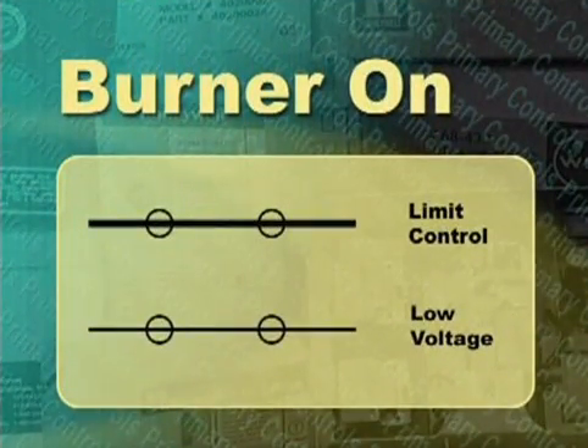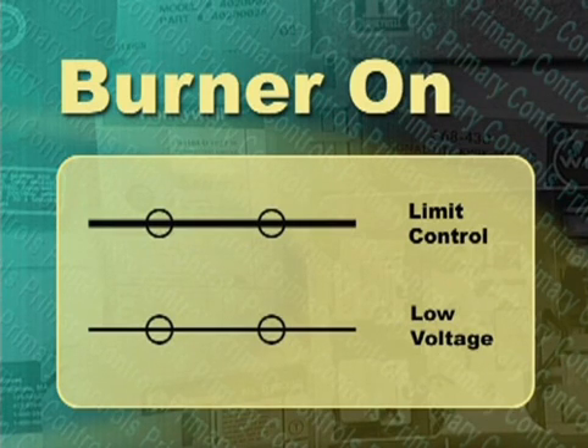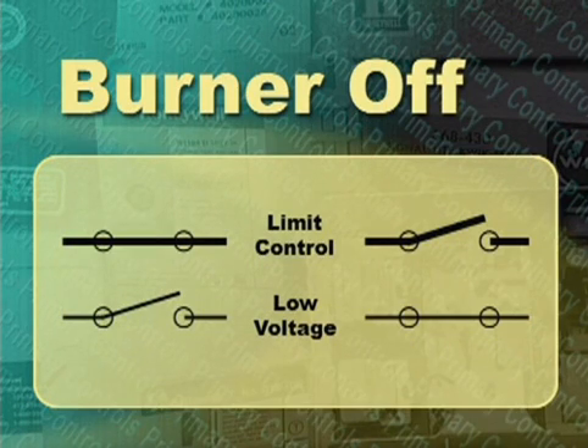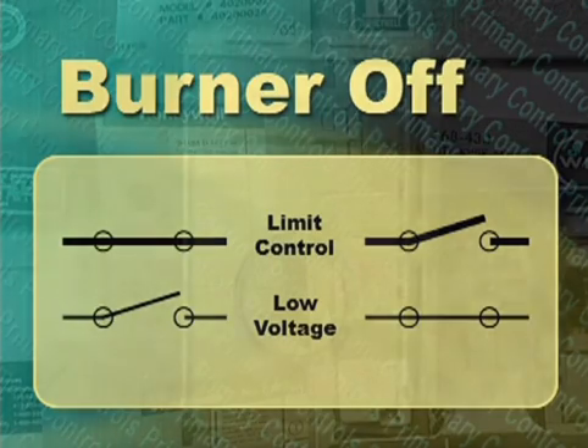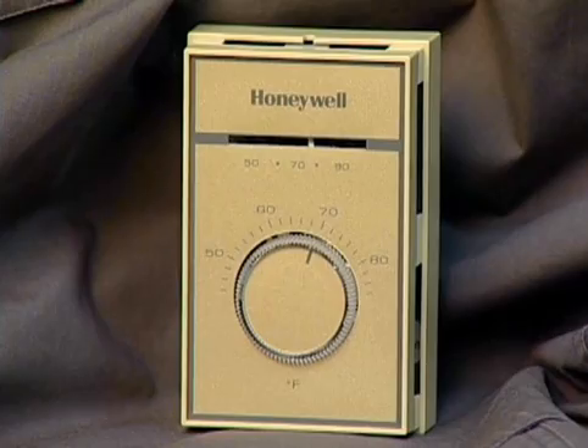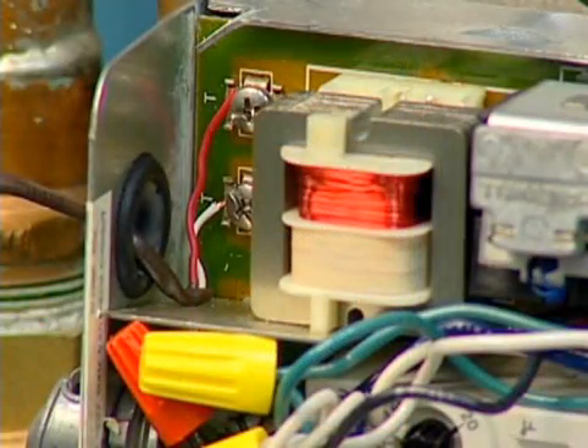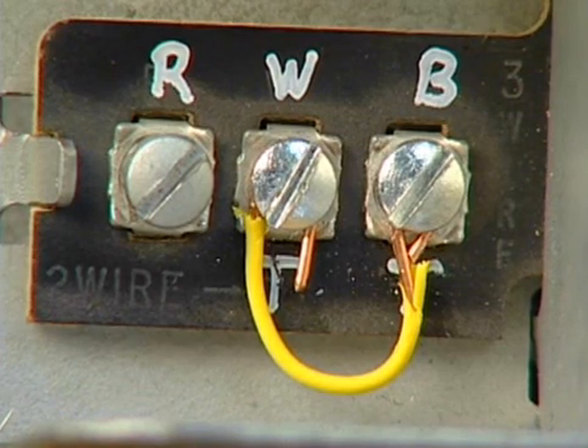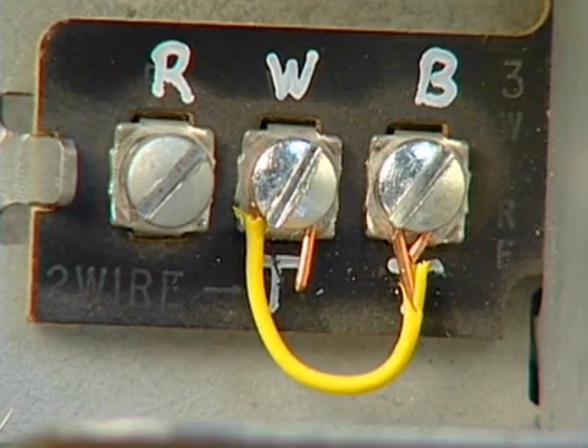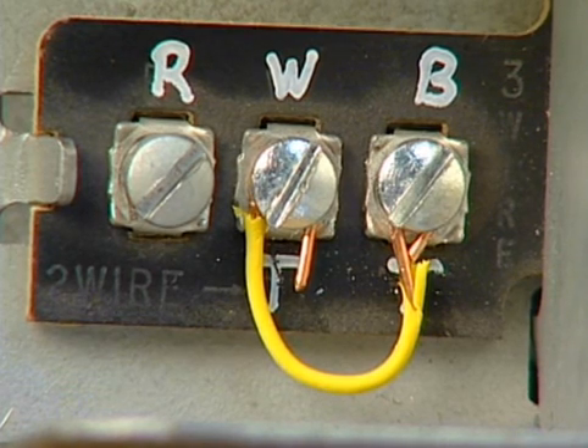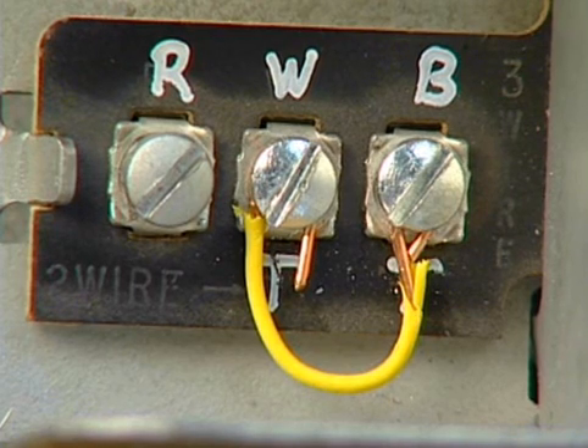For the primary control to activate the oil burner, both the line and low voltage circuits must be closed. In most cases, that means that if either the thermostat or the limit control is satisfied or open, the primary control will not activate the oil burner. In systems with a line voltage thermostat or with a low voltage thermostat connected to controls other than the primary control, a jumper is normally placed between the primary's thermostat terminals, permanently closing the low voltage circuit. The primary control is then activated solely by the limit control.